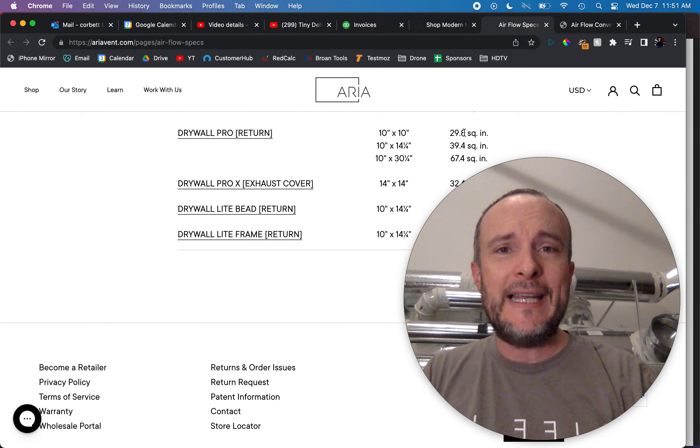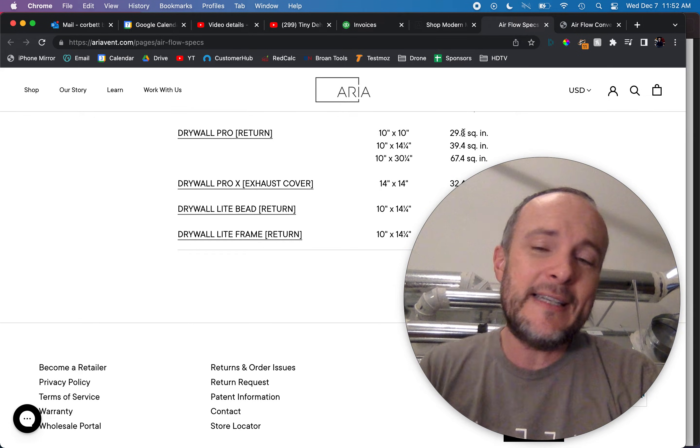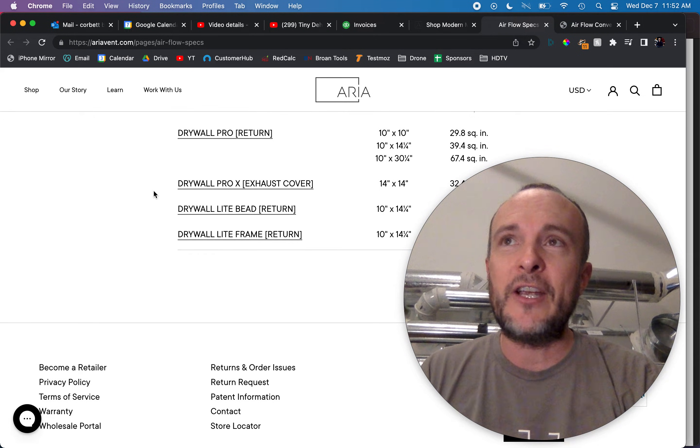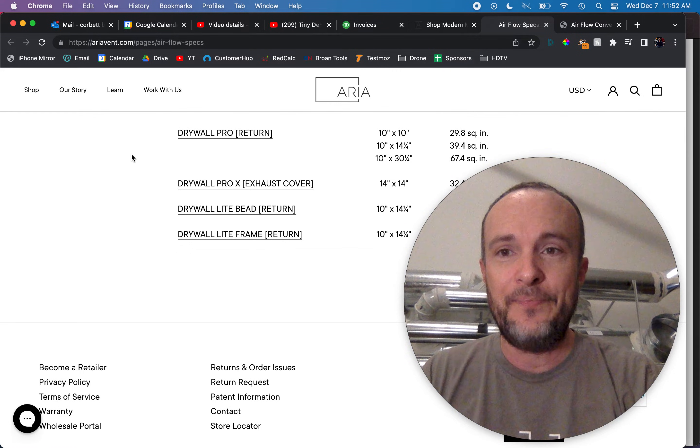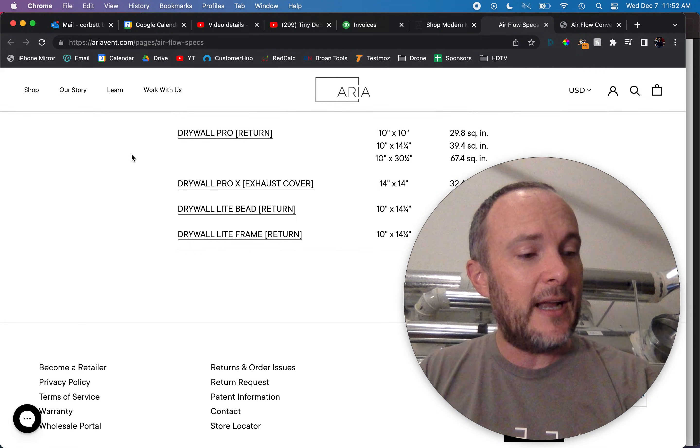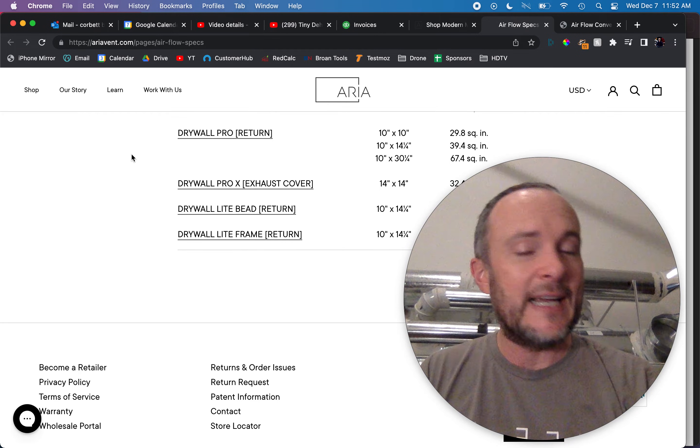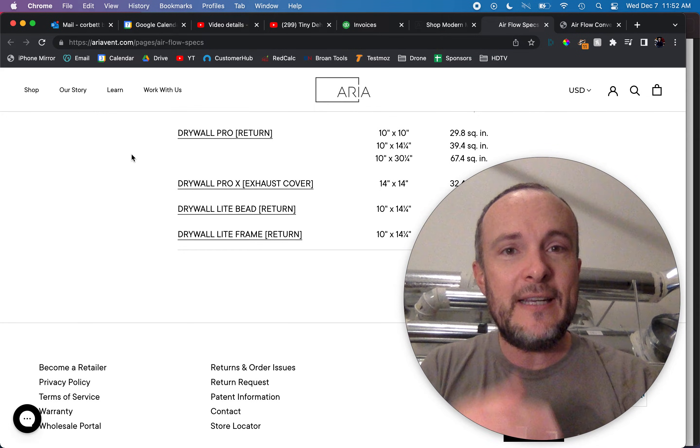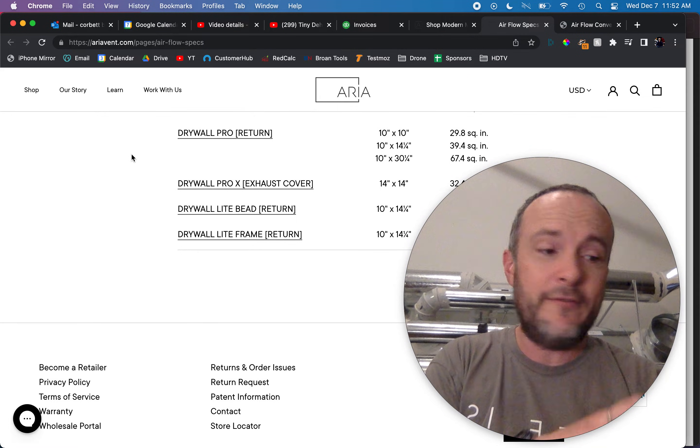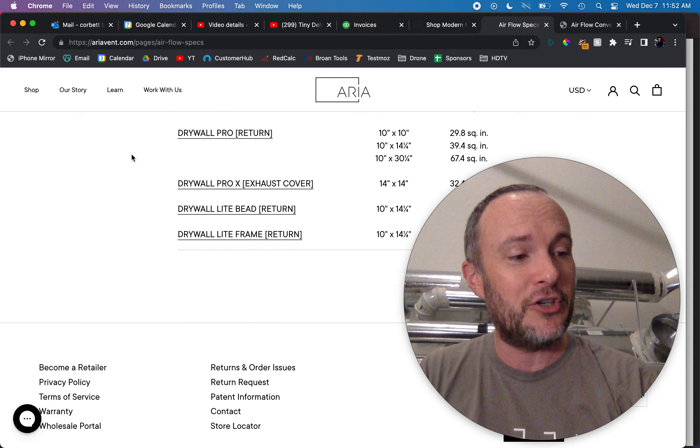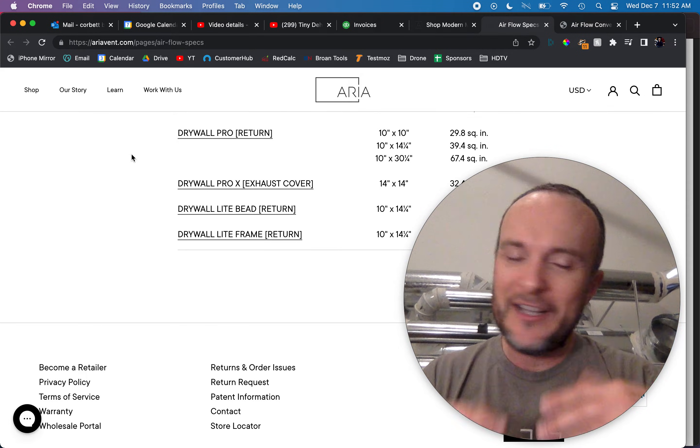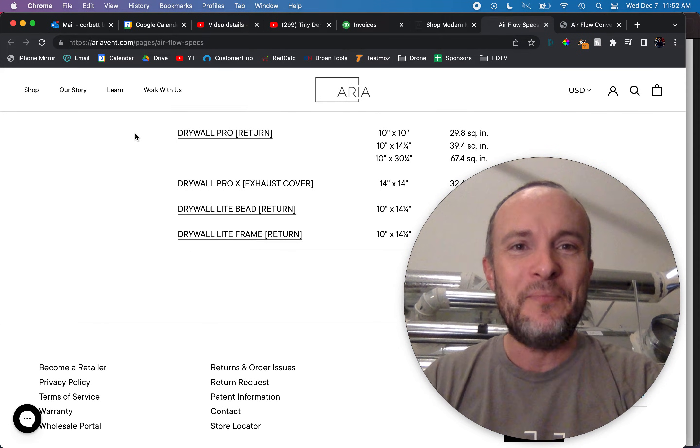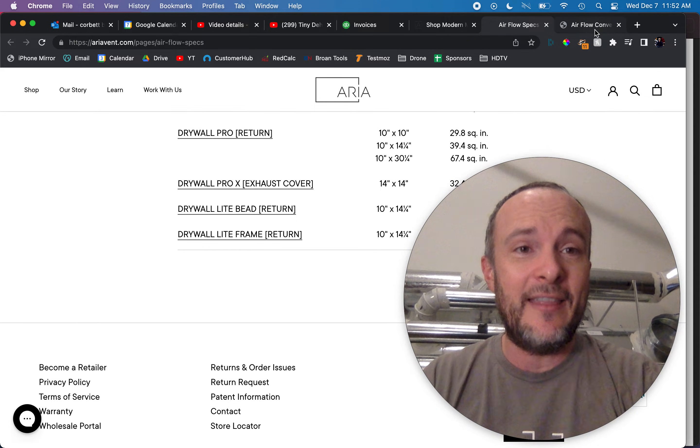In order for him to get his 640, he's got something like a three and a half ton system on his house which has about 1400 CFM. So he's got like a 650 CFM return on one floor and a 750 CFM return on the other floor. And it turned out, I'll spare you the calculations but suffice it to say you can use something like this right here which is at engineering.com to calculate this.